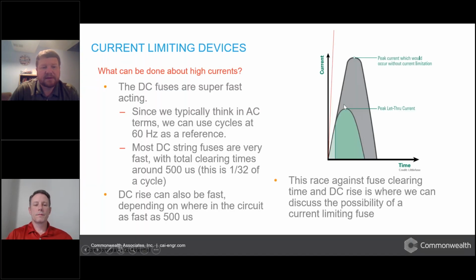All right, thank you, Del. So this would be a good slide here. For those that aren't very experienced with current limiting fuses, first we'll talk a little bit about how they work in the AC world, because that's where most of us live. For a current limiting fuse in the AC world, your AC rises are generally going to be very similar. We run on a 60 hertz system in the United States, and the fuse manufacturers that are building current limiting fuses understand that and build fuse times that are appropriate to that scale.